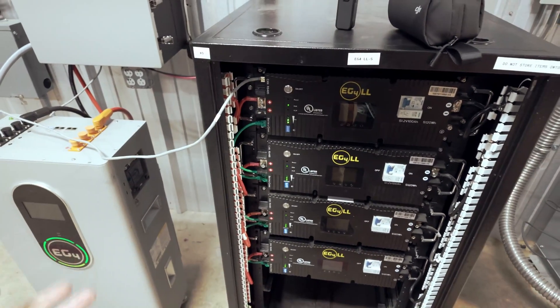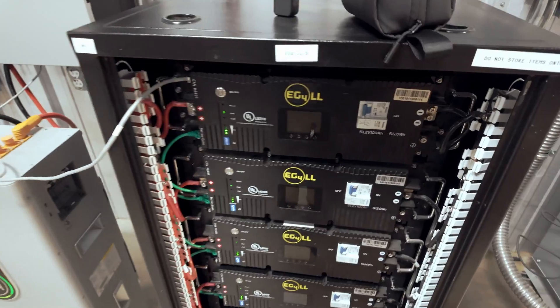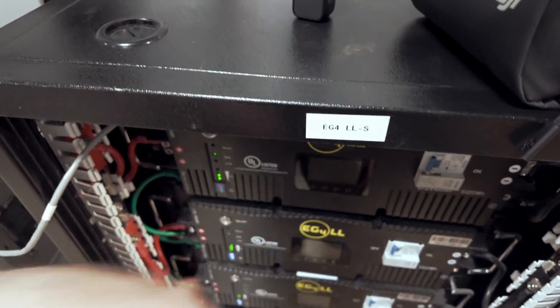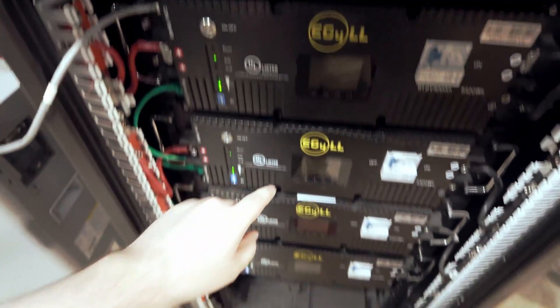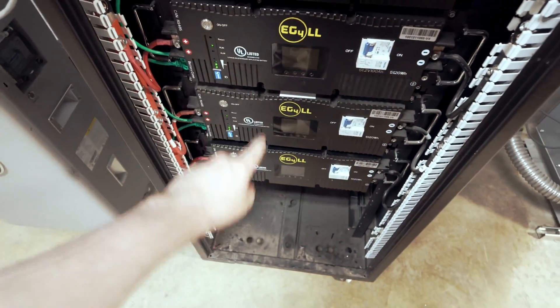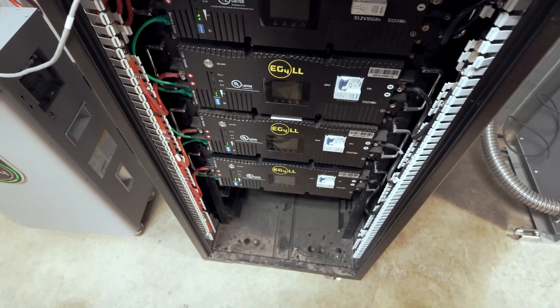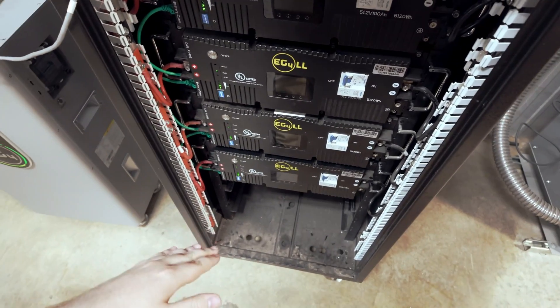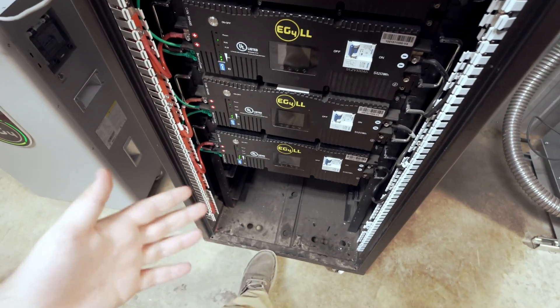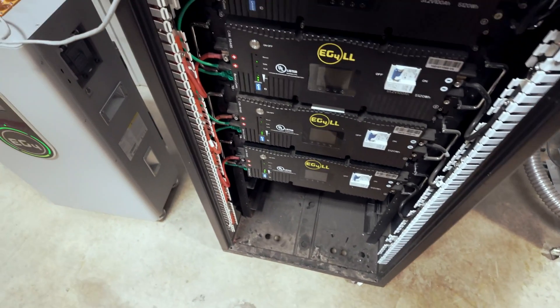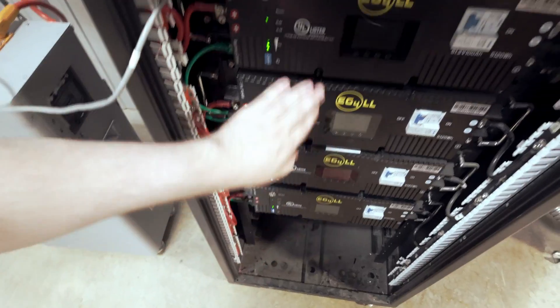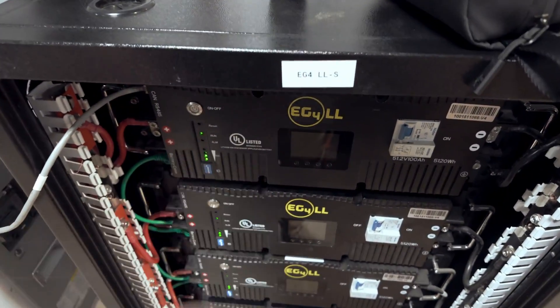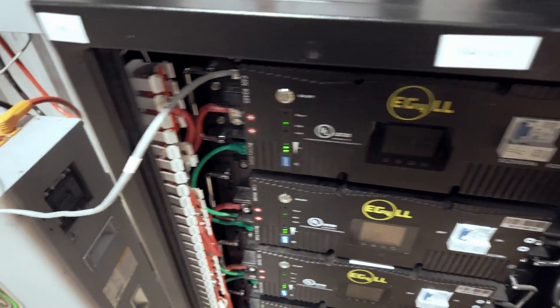What you'll need to do is power cycle your master battery only if you don't see all of your batteries showing up. Because sometimes if you have your master battery communicating with Solark before the rest of your batteries are online, it will not catch the rest of the batteries. It won't know to look for them. So make sure if you see that, you reset the master battery.